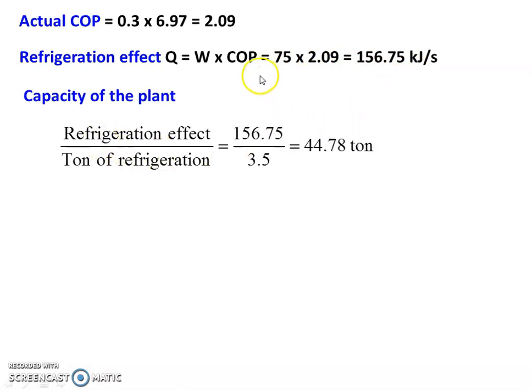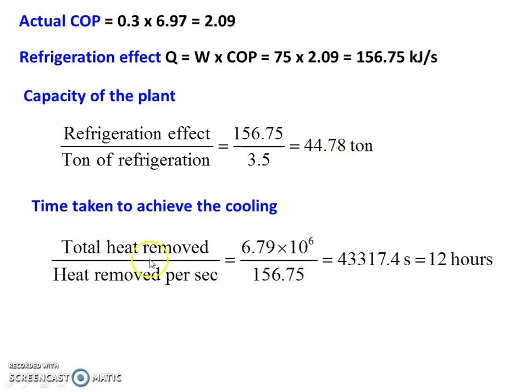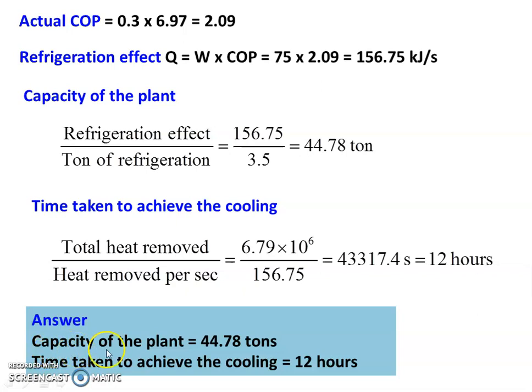Capacity of the plant equals refrigeration effect divided by ton of refrigeration: 156.75 divided by 3.5 equals 44.78 tons. Time taken to achieve cooling equals total heat removed divided by heat removed per second: 6.79 times 10^6 divided by 156.75 equals 43,317 seconds, which equals 12 hours. Answers: capacity of the plant equals 44.78 tons and time taken to achieve the cooling is 12 hours.